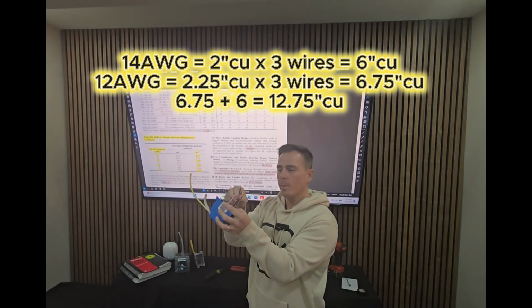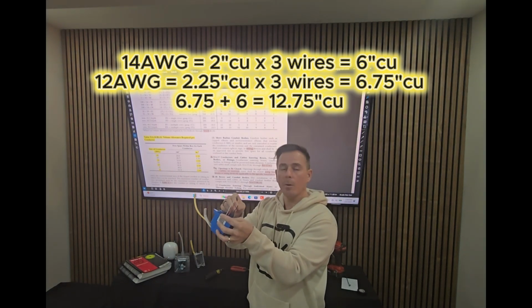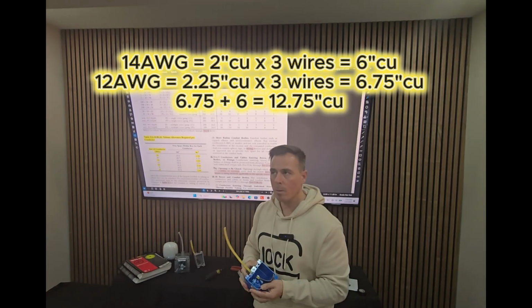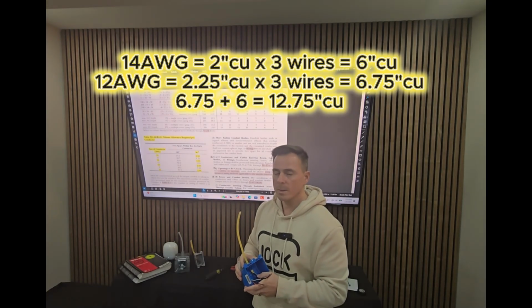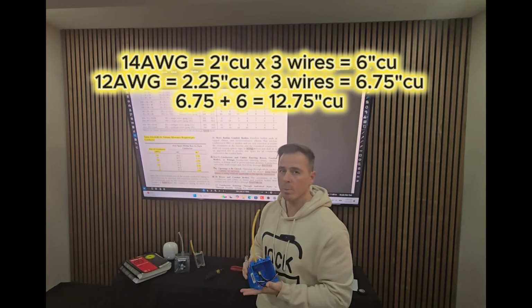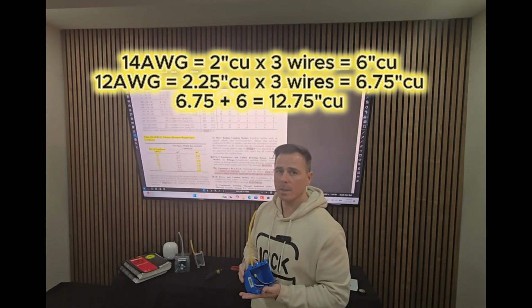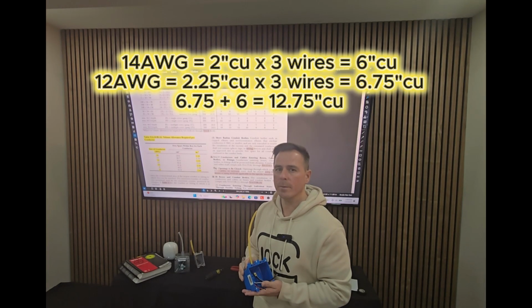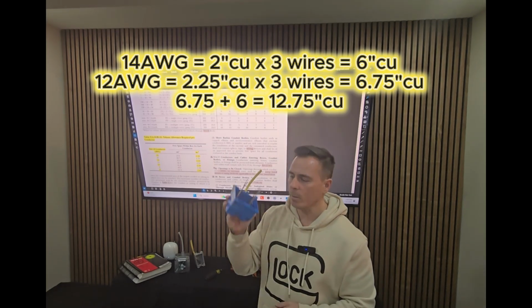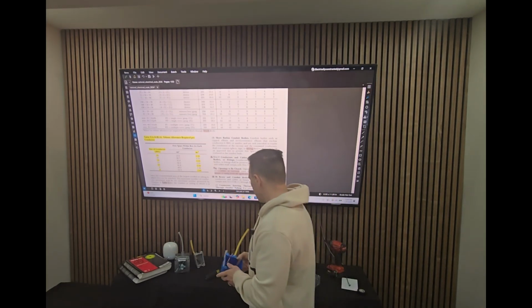So we got our white, we got our black, and we got our grounding conductor. So that's going to equal 6.75. Then we got 6.75 plus 6. It's going to give us 12.75 cubic inches of volume in this box here.